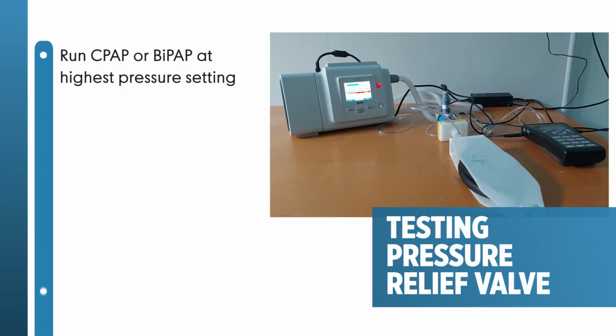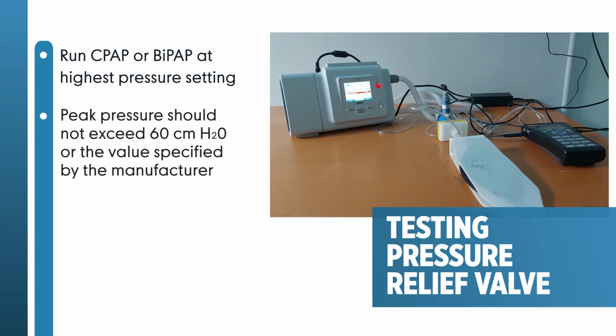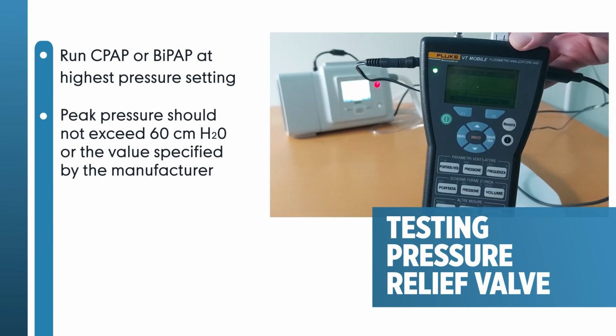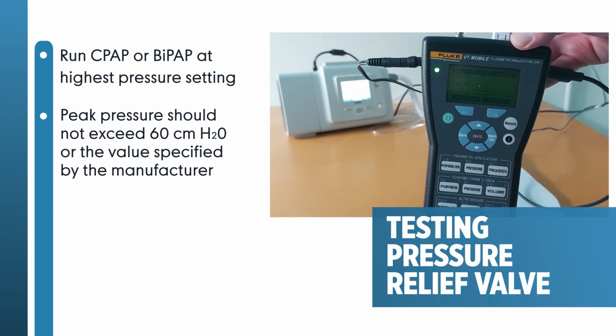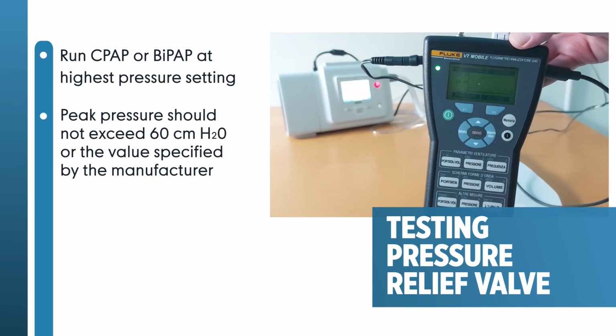To test the pressure relief valve, block the breathing circuit while measuring the pressure at the blockage point. Run the CPAP or BiPAP at the highest pressure setting. The peak pressure should not exceed 60 centimeters of water pressure or the value specified by the manufacturer.